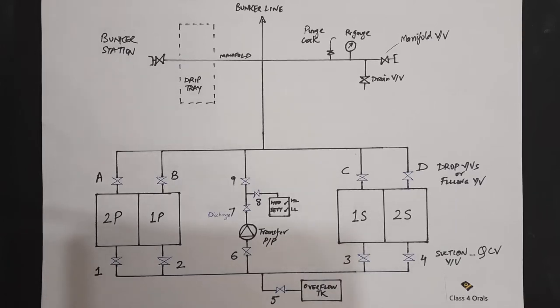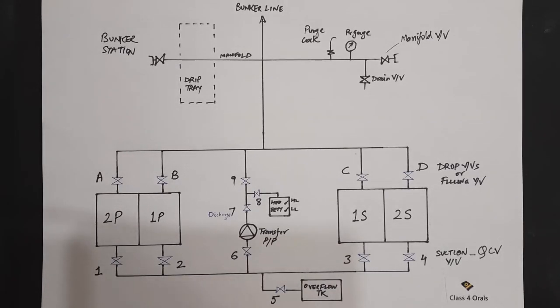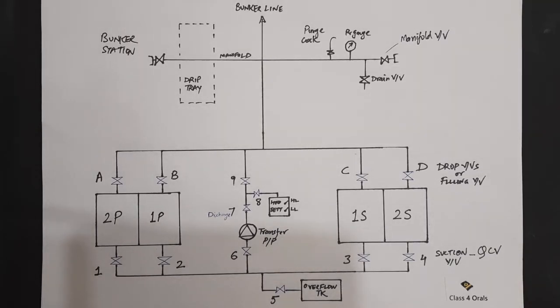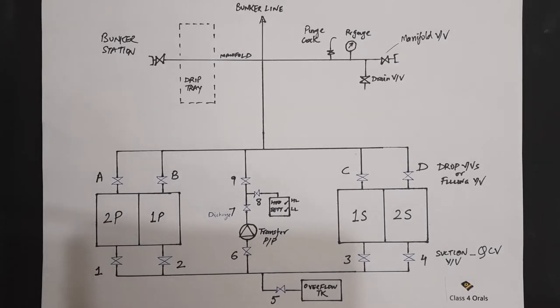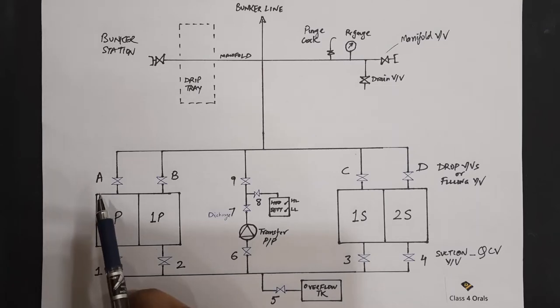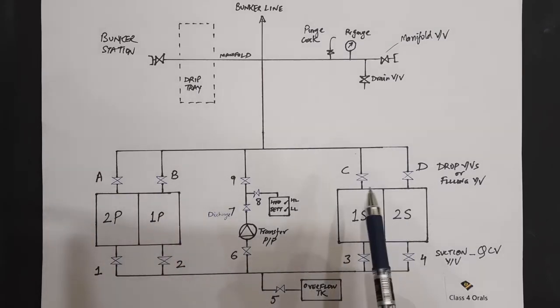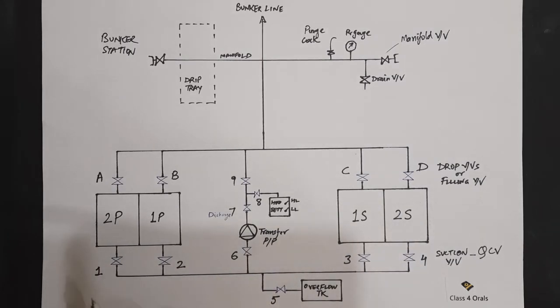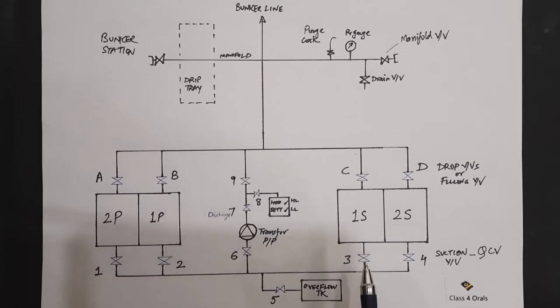Now let us understand this bunker line diagram, which is common on every kind of ship. This is the basic illustration of the bunker line. So what we are having? We can see there are four tanks: one port, two port, one starboard, two starboard with individual filling valves or drop valves. Namely A, B, C and D. Each one is having the suction valve which is 1, 2, 3 and 4. And these suction valves are quick closing valve and they are not non-return valve.